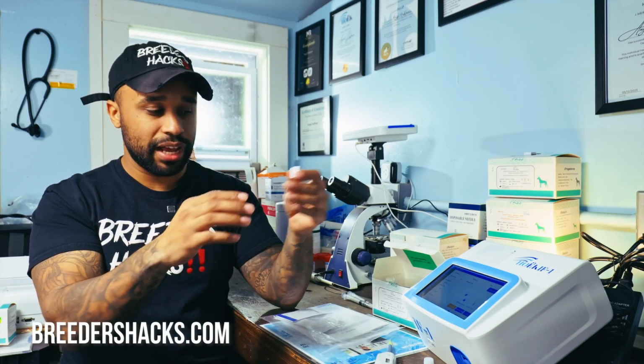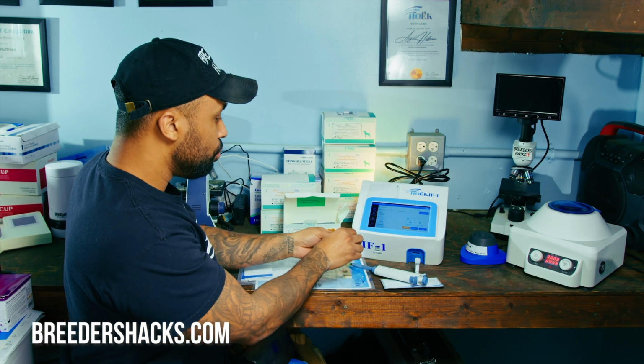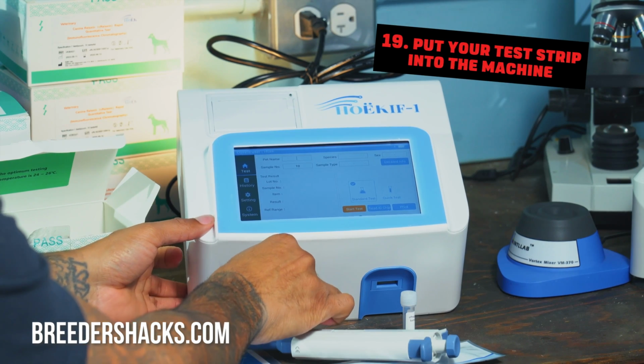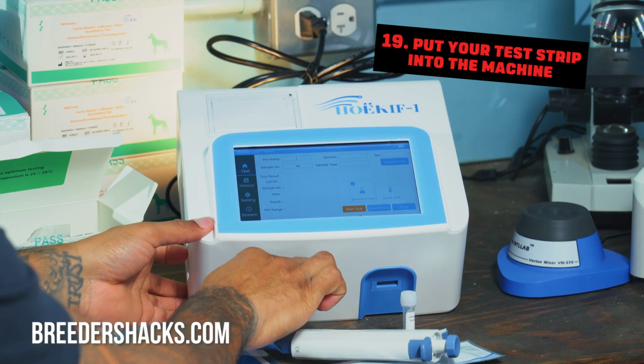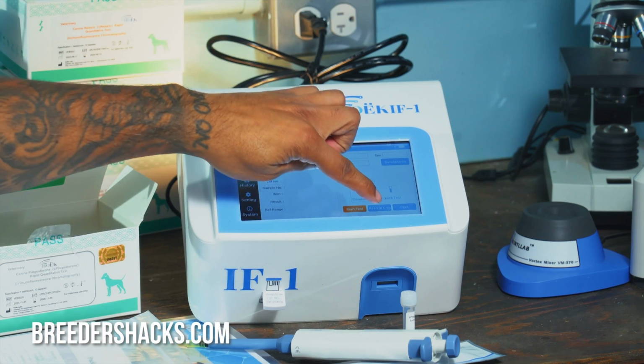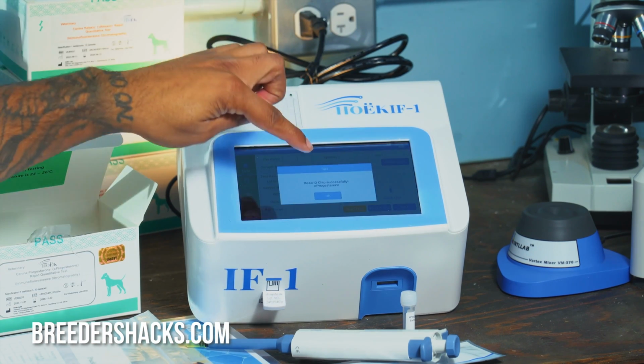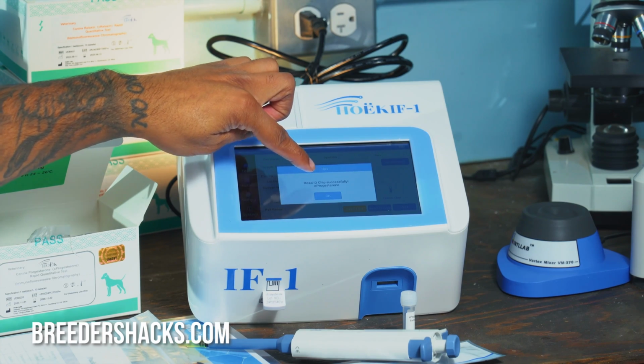Does the machine need some kind of calibration? No, this is the calibration. Literally all you have to do is put this inside your machine, right where it says ID chip, slide it in just like that, and hit read ID chip. Now it says read ID chip successfully for progesterone.